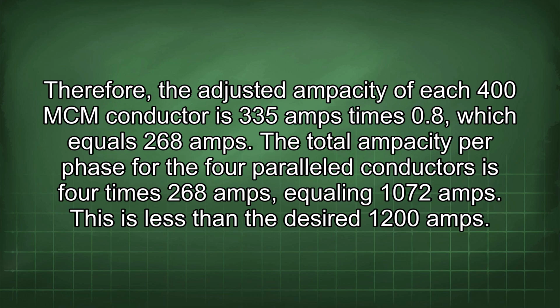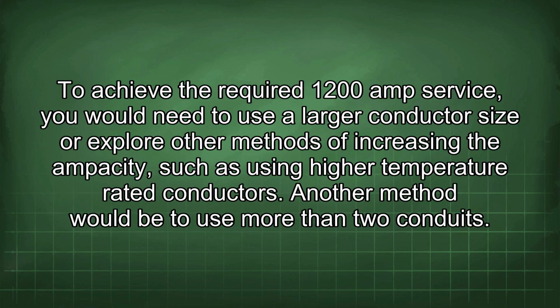The total ampacity per phase for the 4 parallel conductors is 4 times 268 amps, equaling 1072 amps. This is less than the desired 1200 amps. To achieve the required 1200 amp service, you would need to use a larger conductor size or explore other methods of increasing the ampacity, such as using higher temperature rated conductors. Another method would be to use more than 2 conduits.